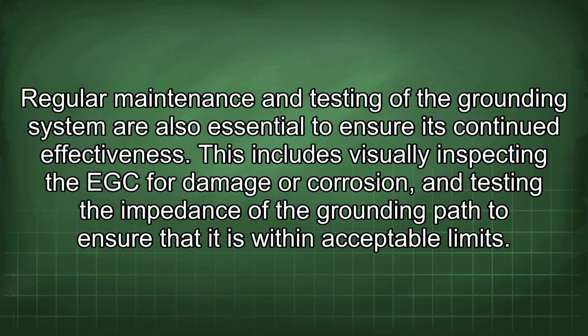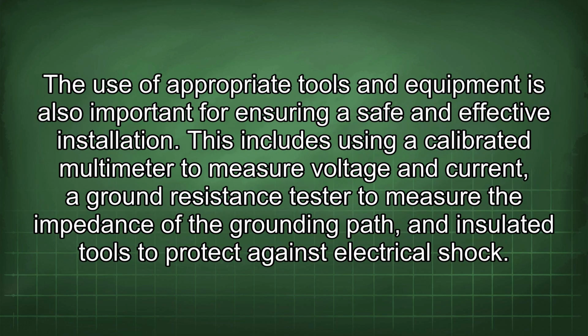Regular maintenance and testing of the grounding system are also essential to ensure its continued effectiveness. This includes visually inspecting the EGC for damage or corrosion and testing the impedance of the grounding path to ensure that it is within acceptable limits. The use of appropriate tools and equipment is also important for ensuring a safe and effective installation. This includes using a calibrated multimeter to measure voltage and current, a ground resistance tester to measure the impedance of the grounding path, and insulated tools to protect against electrical shock.